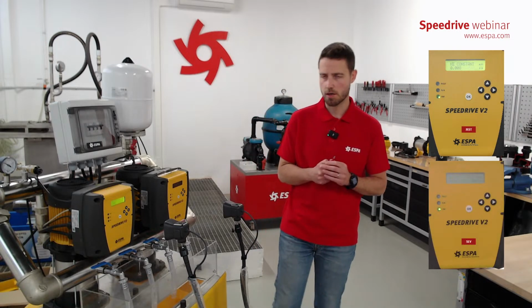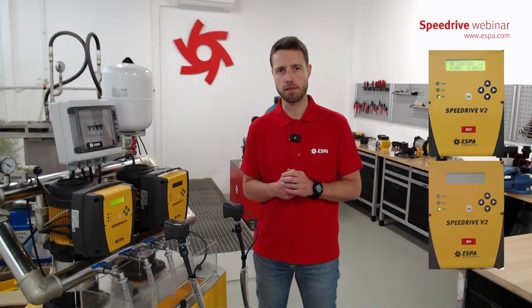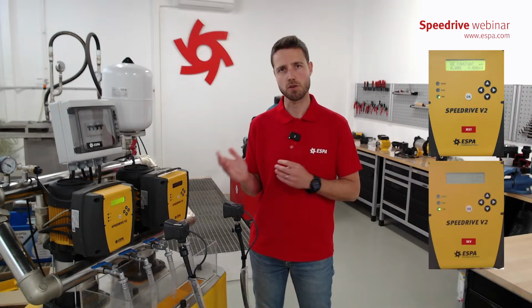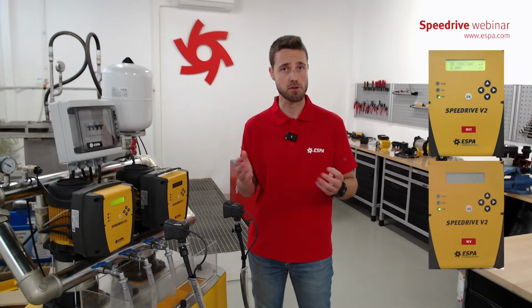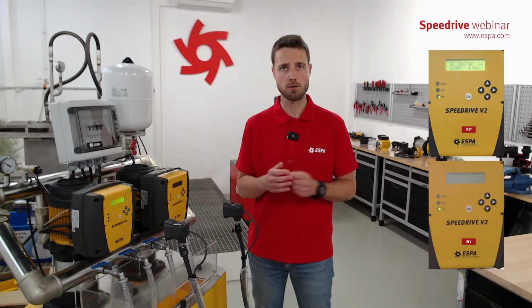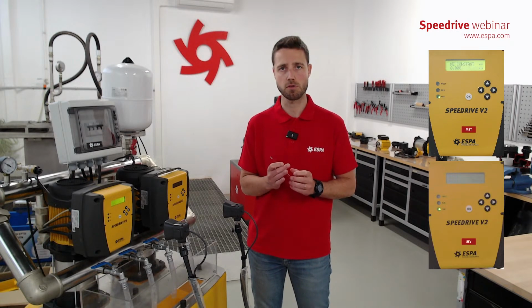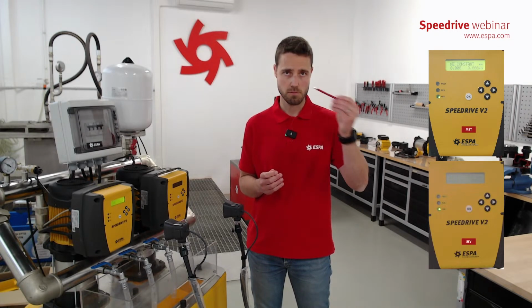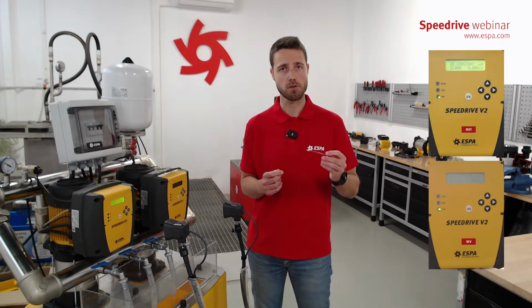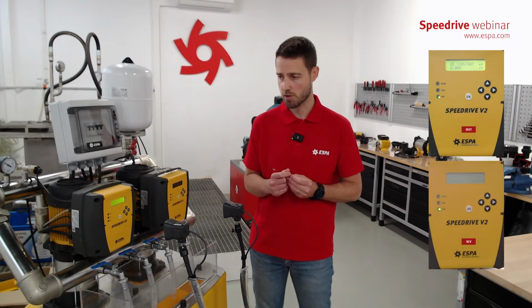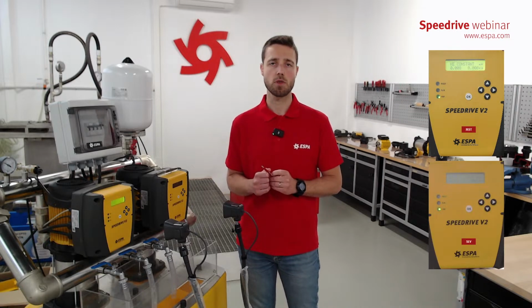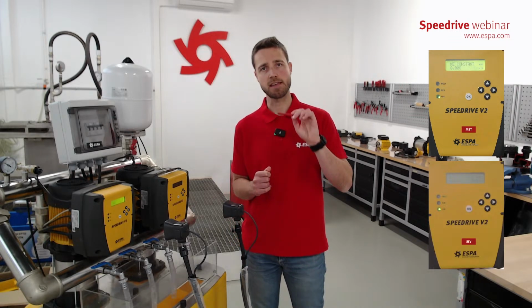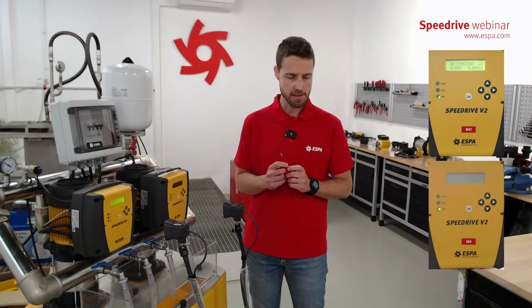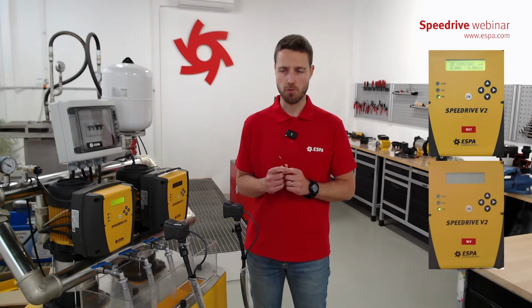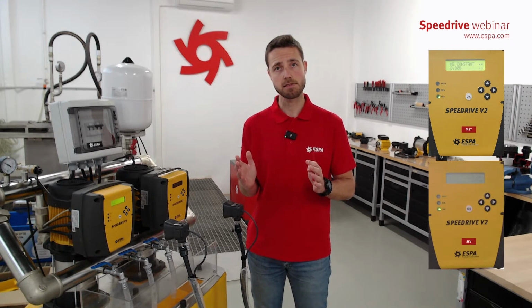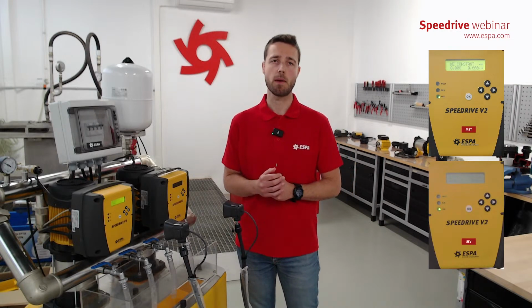System control, you can see it in many different applications, not just for engines, also for temperature control. Probably in your house you have a monitor of temperature. Once we reach a temperature, there is always a system control in order to increase or decrease the temperature. So it's the same with a VFD. We have to maintain a pressure. And how does a VFD exactly work? In this case, we have set 3 bars, if you remember.